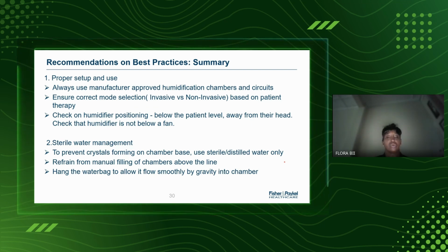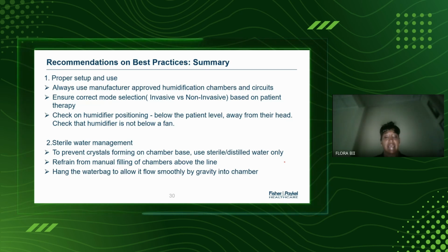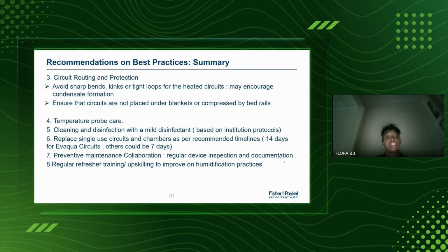Sterile water management, just to re-emphasize that we use distilled water or sterile water, not saline, and no medicated fluids, as I had mentioned earlier. Now, other recommendations would be on checking of circuits. This is a recap as well, just checking that you don't have any kinking, any tight loops, which might encourage condensate forming, and also just temperature probe care. Sometimes you find that probes break, and so you always need to be very attentive to check that you have the temperature and flow probes and the heater wires working optimally. Cleaning with a mild disinfectant, checking as well the type of circuits that you're using, and just regular upskilling with both the biomedical team in collaboration as well with the infection control and also the nursing team.